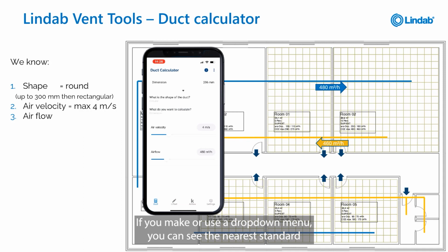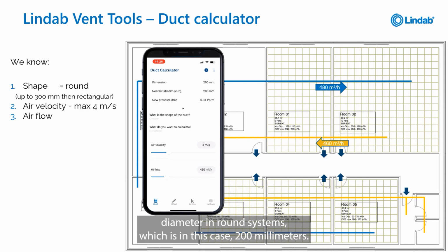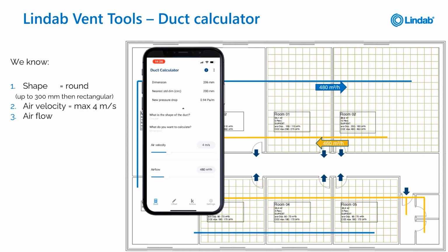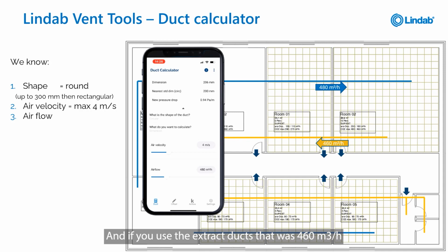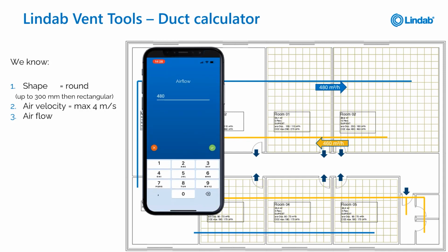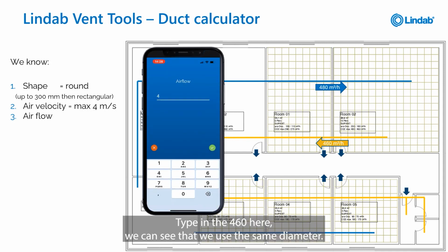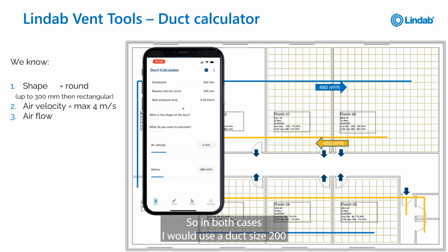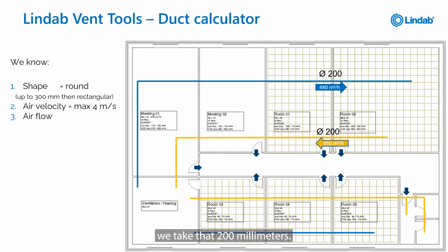If you use a drop-down menu, you can see the nearest standard diameter in round systems, which is in this case 200 millimeters. And if you use the extract duct with 460, type in the 460 here, we can see that we use the same diameter. So in both cases, I would use a duct size of 200. Okay, we take the 200 millimeters.